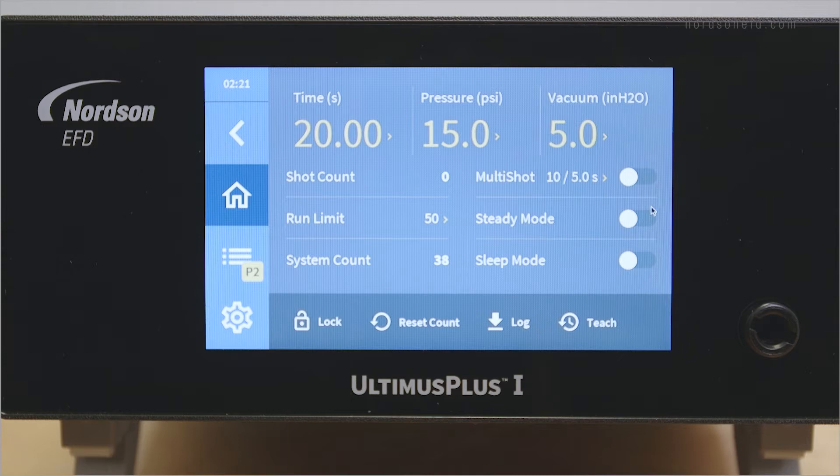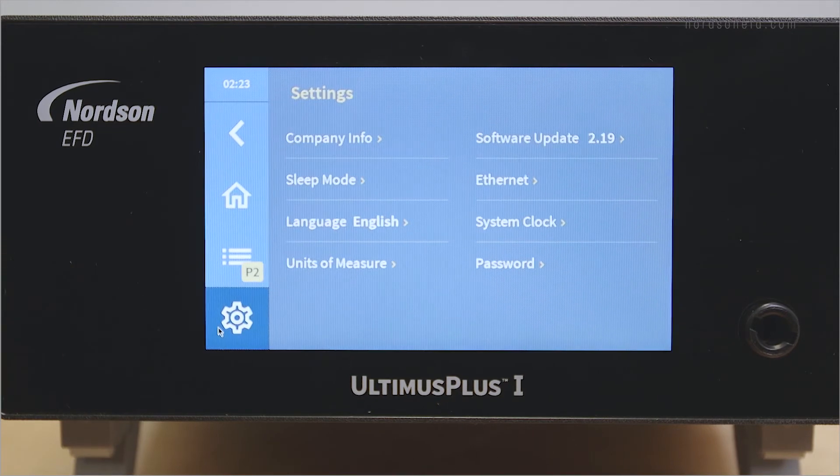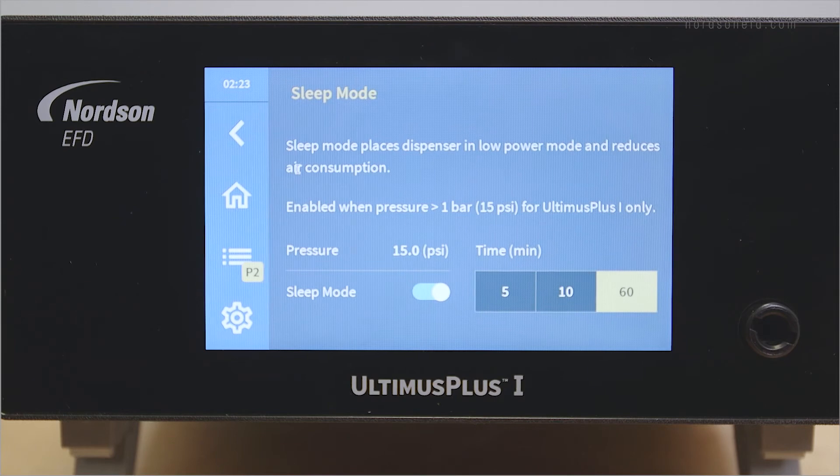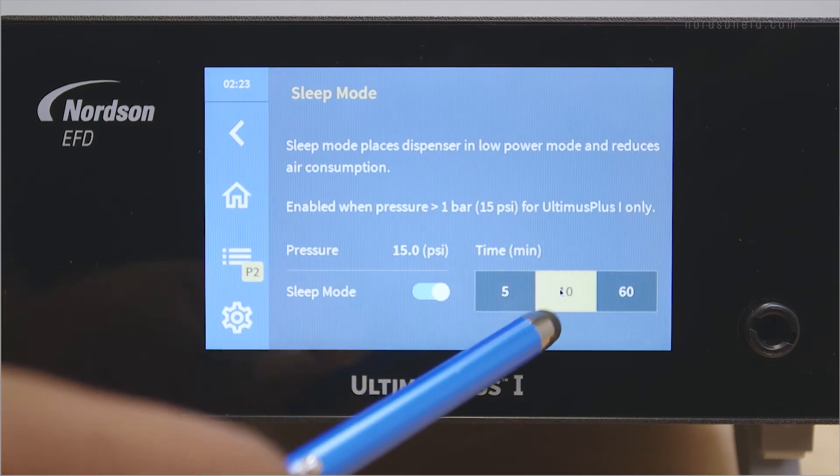Sleep mode is only available on the UltimusPlus I and can only be enabled when the fluid pressure is above 15 psi. It allows the end user to reduce power and air consumption if the dispenser hasn't been running for a long period of time. To enable sleep mode, move the sleep mode switch to on. To change sleep mode settings, press the settings button and then press sleep mode. You can set your sleep mode timer for 5, 10, or 60 minutes.